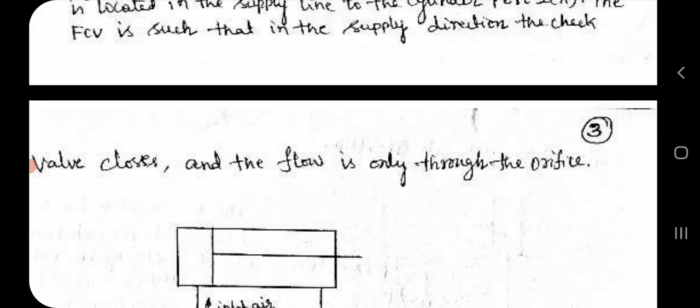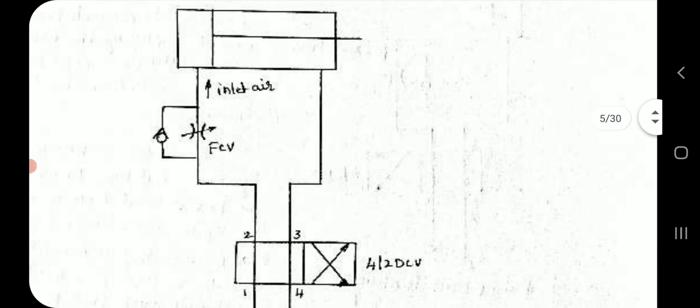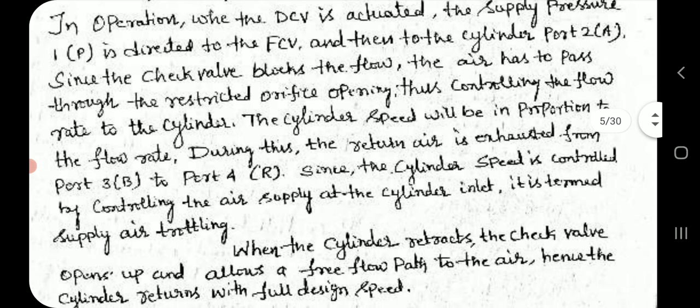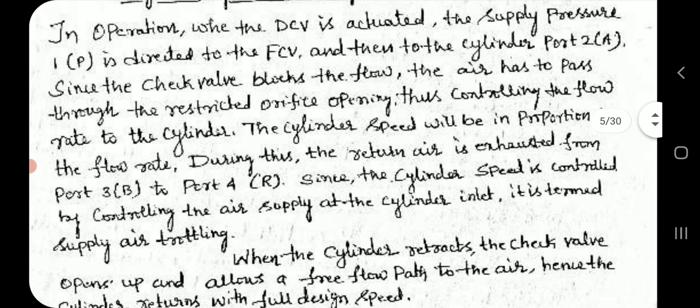The flow control valve is such that in the supply direction, the check valve closes and the flow is only through the orifice. In operation, the direction control valve is actuated and the supply pressure is directed to the flow control valve and then to the cylinder port. Since the check valve blocks the flow, the air has to pass through the restricted orifice opening, thus controlling the flow rate to the cylinder. The cylinder speed will be in proportion to the flow rate.